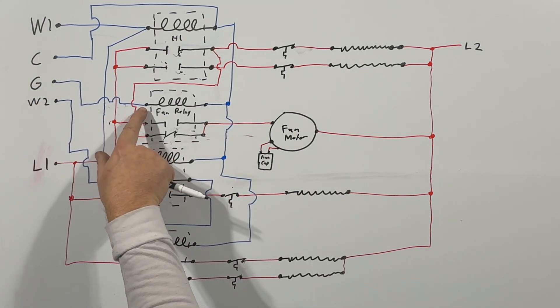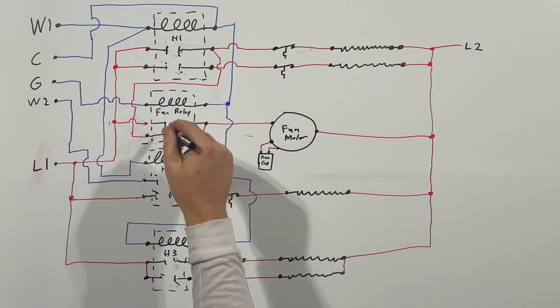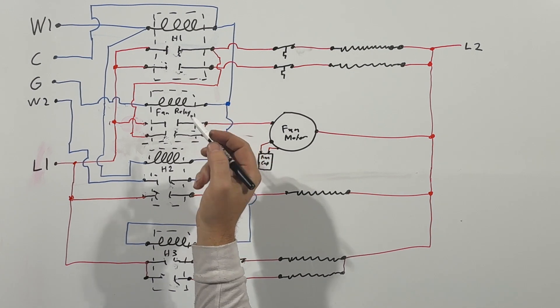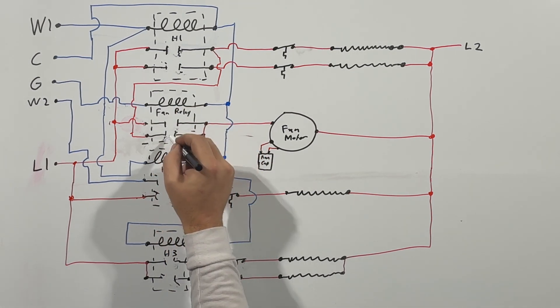Well, if W1 is not energized, we have no high voltage going to the fan motor, so it won't turn on. So what we do is we connect our G directly to the fan relay coil, and that will energize this.